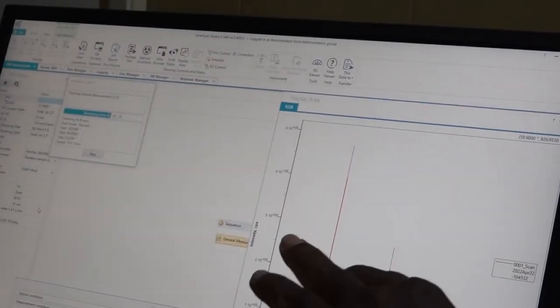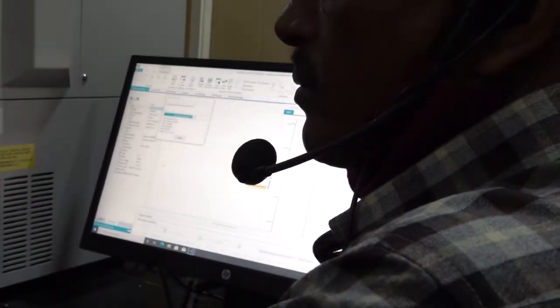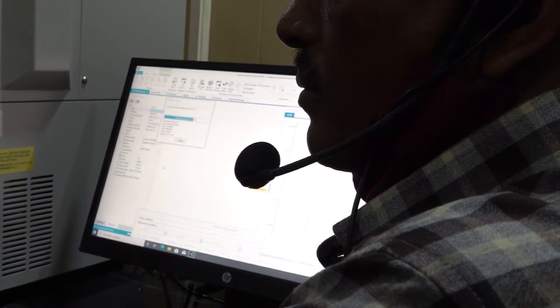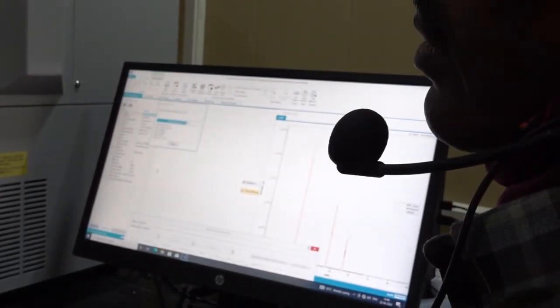Every time, no need to go to the X-ray aging. Only in the morning, when you come around 9 o'clock, you can start this aging. I think it will take maybe around 6-7 minutes maximum. After that you can continue with your sample. So that protocol which has been set can be used for everything. For aging, that protocol can be used every time. Yeah, every day morning you can use it.